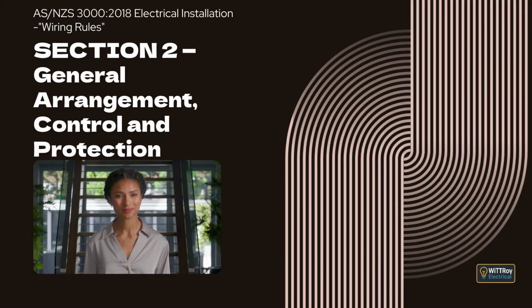Clause 2.3.2 Common Control Requirements. Clause 2.3.2.1 General. This clause explains that every circuit must be capable of being isolated from all of its supply conductors. Depending on the system, this may be done by isolating all conductors or by isolating only the conductors that must be disconnected for safety.